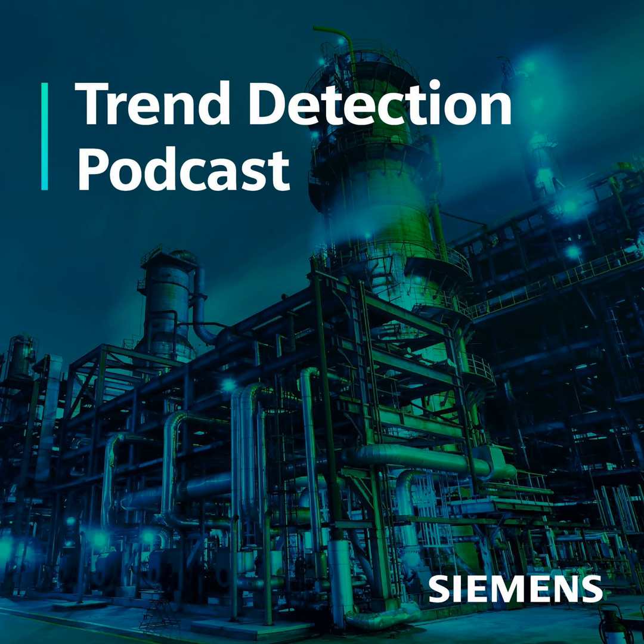And even those small things operationally, the way solder systems have panels over the top of them that they open up. Yes. And so one of the measures we look at is the O2 in the atmosphere, isn't it? But of course, when they open the door, that drops. Yeah, so we're looking at that in the data set thinking, oh, something's gone really wrong, but actually no, it's fine.